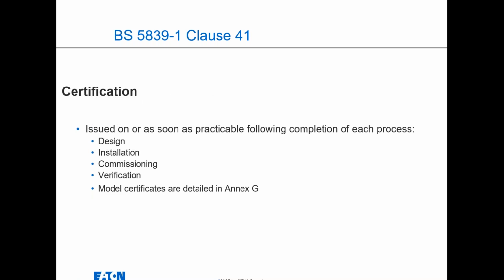And those are the models of certification. So in the standards, it's models G1, G2, G3, and G4, which are in Annex G for your design, install, commissioning, and verification. The verification is if you make alterations to the system after install. So if you had an L2 system and you wanted to upgrade that to an L1 system, you do that work, and you then have a verification certificate to say that it's compliant to L1 now, just to basically keep the journey intact.